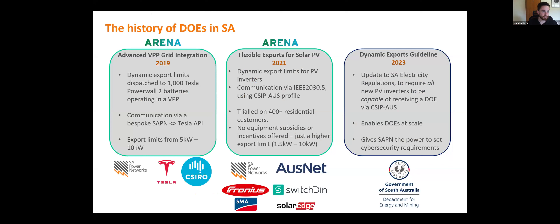The history of DOEs in SA: we started this journey back in 2017, doing brainstorming in this area. In 2019 we launched an ARENA-funded project with Tesla and the CSIRO called Advanced VPP Grid Integration — working with Tesla to generate and communicate DOEs to a thousand Tesla Powerwall 2 batteries operating as part of a state government-funded VPP. Communication was via a bespoke SAPN-to-Tesla API, and export limits went from 5 kW to 10 kW, effectively doubling their export limit. This was our first real demonstration of a DOE.